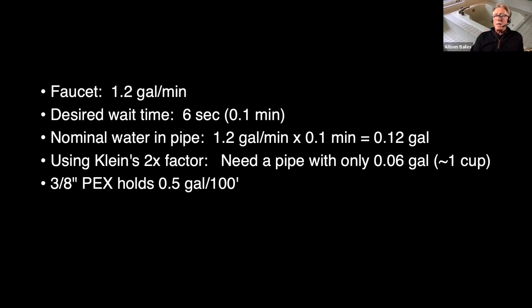With 3/8 inch PEX, if I replace my 3/4 inch copper with 3/8 inch PEX, which holds 0.5 gallon per 100 feet, to get it in 6 seconds I would have to have no more than 12 feet of pipe.